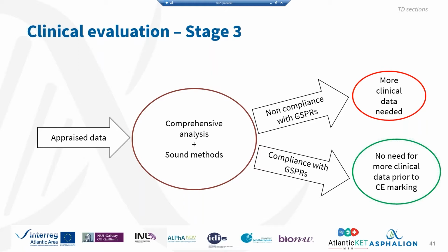If you conclude that it doesn't comply with safety and performance requirements, obviously you will have to go through more clinical data. That doesn't mean that the data up until now is bad. It doesn't mean that your device is not safe. Maybe there is just not enough data to justify the safety of your device, and maybe you have to perform a clinical investigation on your own to demonstrate it. If, on the other hand, you consider that it complies with the requirements on safety and performance, you can proceed with the CE marking.